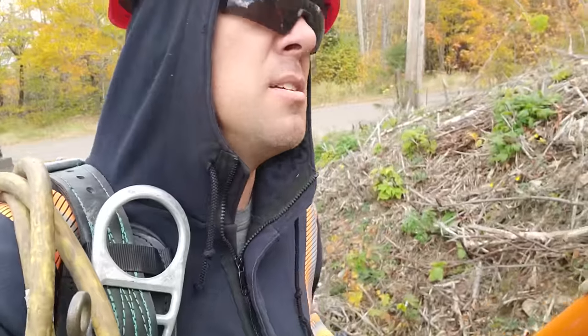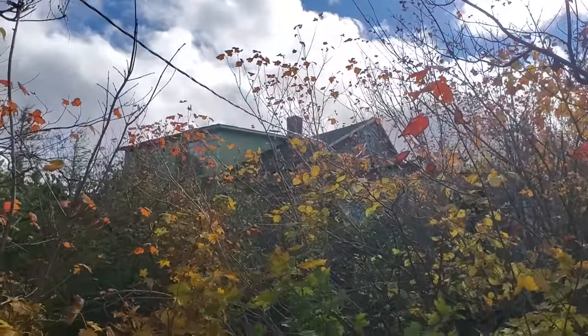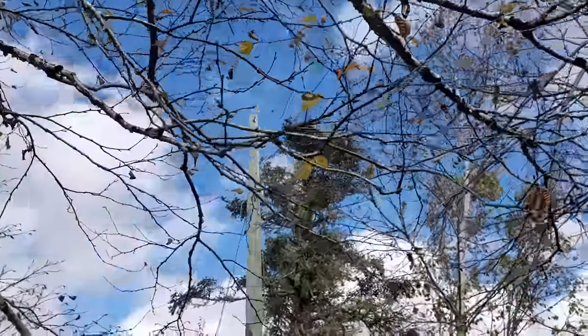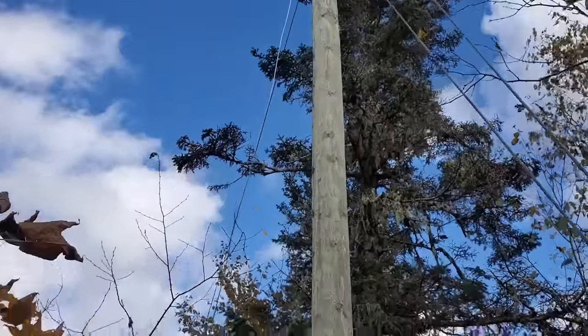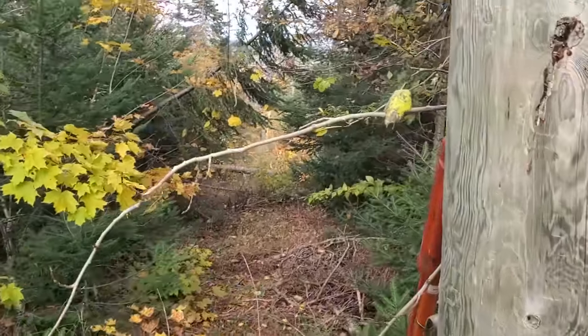Let's head back into the work area. So we're up here now — man, that was a heck of a hike. I'll show you the house right in there. I'm not going to walk through that mess again but trust me when I say it's completely dilapidated — that'll never be hooked up again. The triplex is still attached to the pole, and we can see the primary is still attached on this end coming down to the ground. That's why we didn't walk straight up that easement because of the down primary.